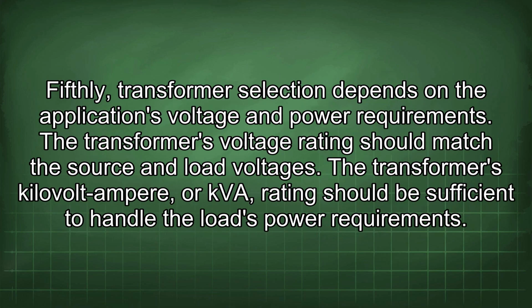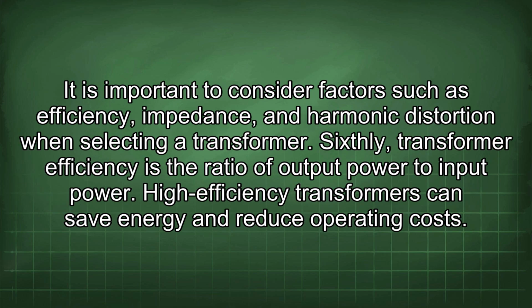Fifthly, transformer selection depends on the application's voltage and power requirements. The transformer's voltage rating should match the source and load voltages. The transformer's kilovolt-ampere, or kVA, rating should be sufficient to handle the load's power requirements. It is important to consider factors such as efficiency, impedance, and harmonic distortion when selecting a transformer.